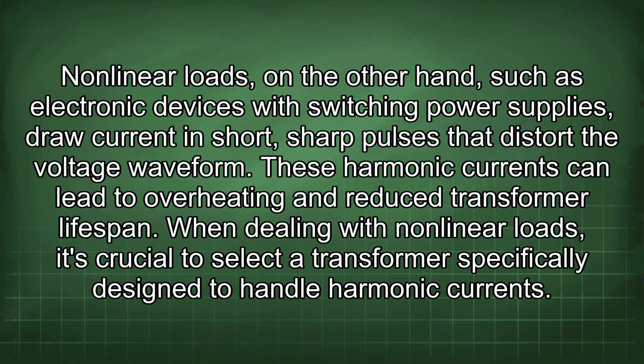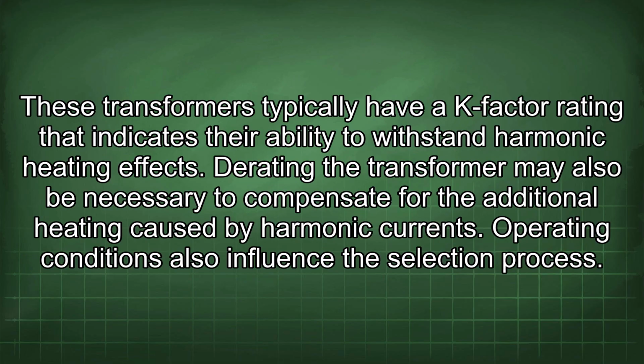When dealing with nonlinear loads, it's crucial to select a transformer specifically designed to handle harmonic currents. These transformers typically have a K-factor rating that indicates their ability to withstand harmonic heating effects. Derating the transformer may also be necessary to compensate for the additional heating caused by harmonic currents.